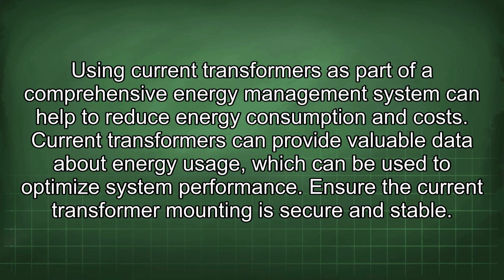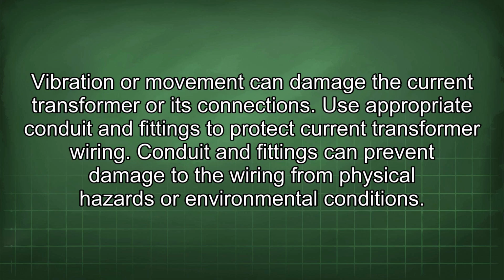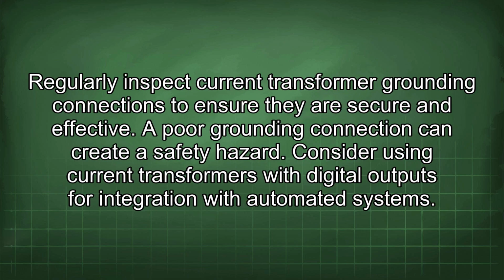Ensure the current transformer mounting is secure and stable. Vibration or movement can damage the current transformer or its connections. Use appropriate conduit and fittings to protect current transformer wiring. Conduit and fittings can prevent damage to the wiring from physical hazards or environmental conditions. Regularly inspect current transformer grounding connections to ensure they are secure and effective. A poor grounding connection can create a safety hazard.